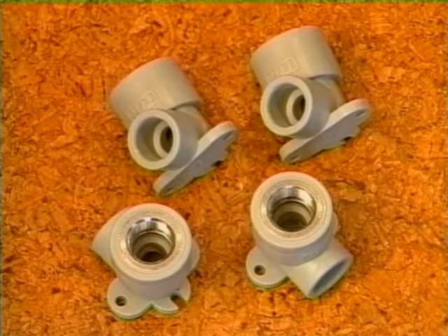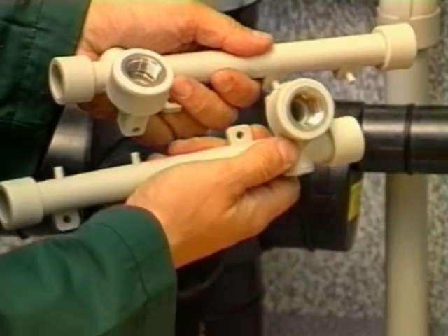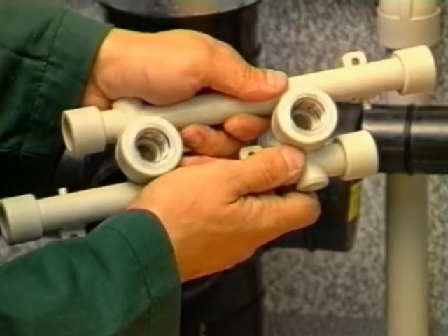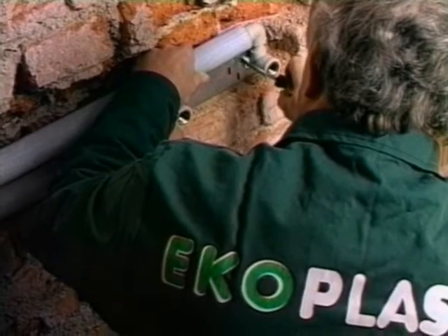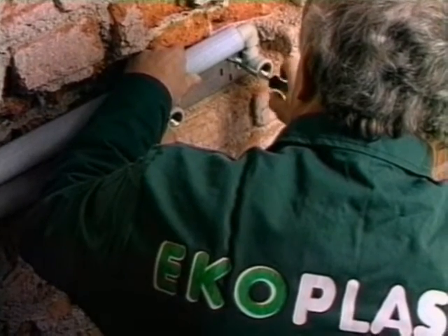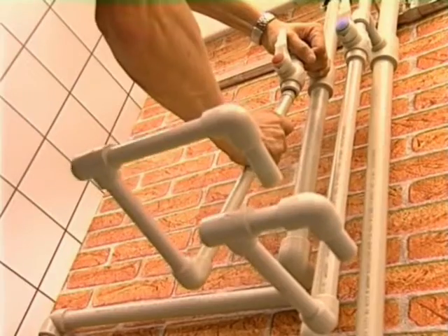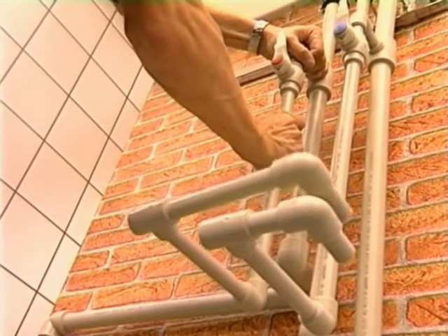Where joining pipes end at a discharge fitting, an independently wall-mounted elbow can be used, or a universal wall unit which can be adapted to a 100mm or 150mm tap unit. An independently wall-mounted elbow is mounted on a fixed support which keeps the shaped piece firmly in the same position. Where a pipe joins to the riser pipe, it is necessary to consider the expansion of both parts. Lead-off pipes from 2 parallel risers are executed using a special crossover shape.